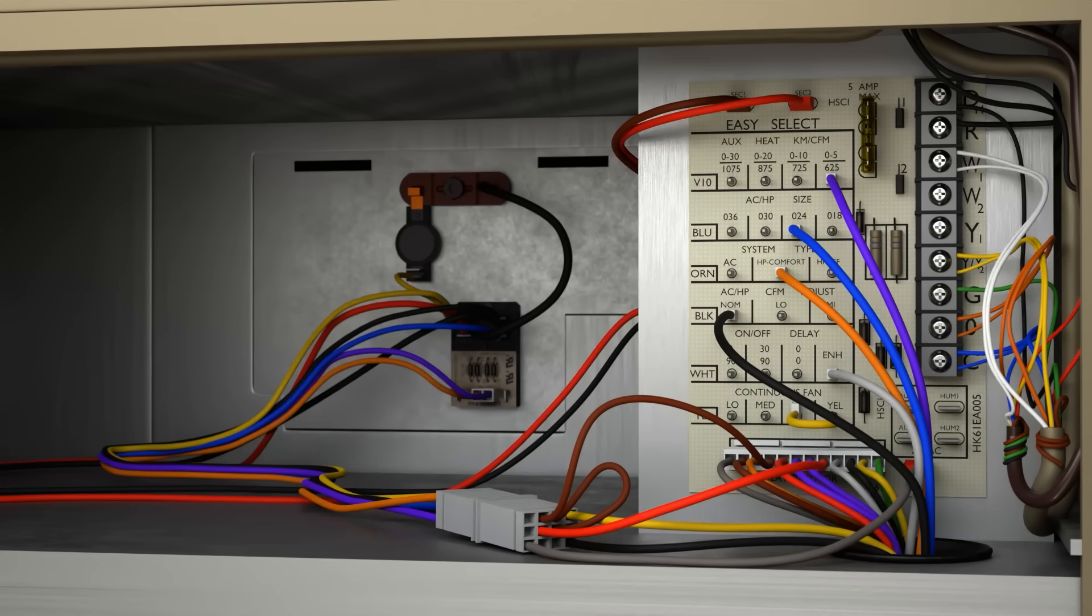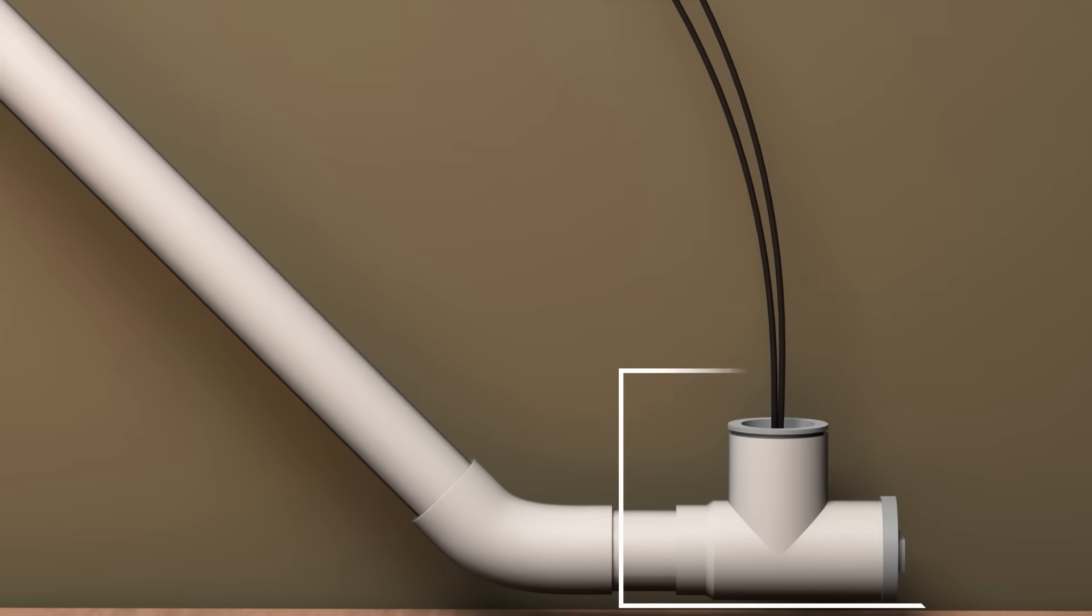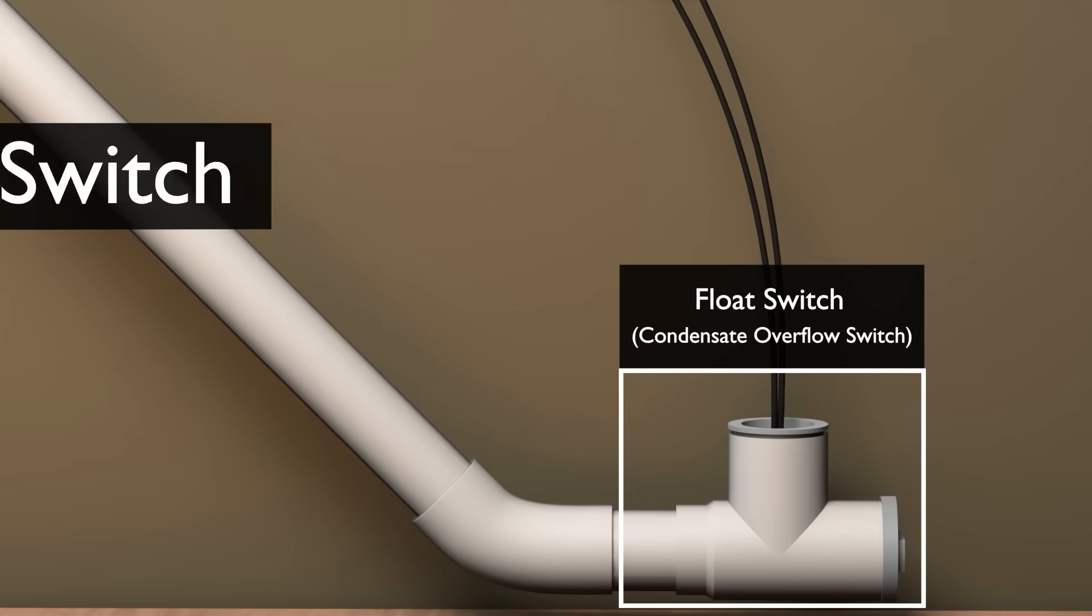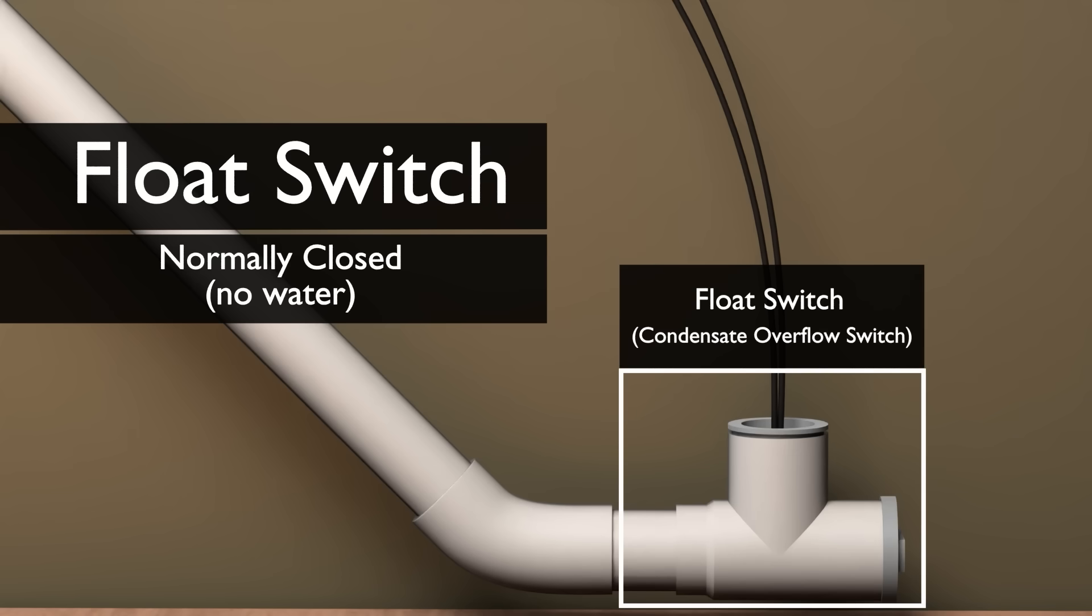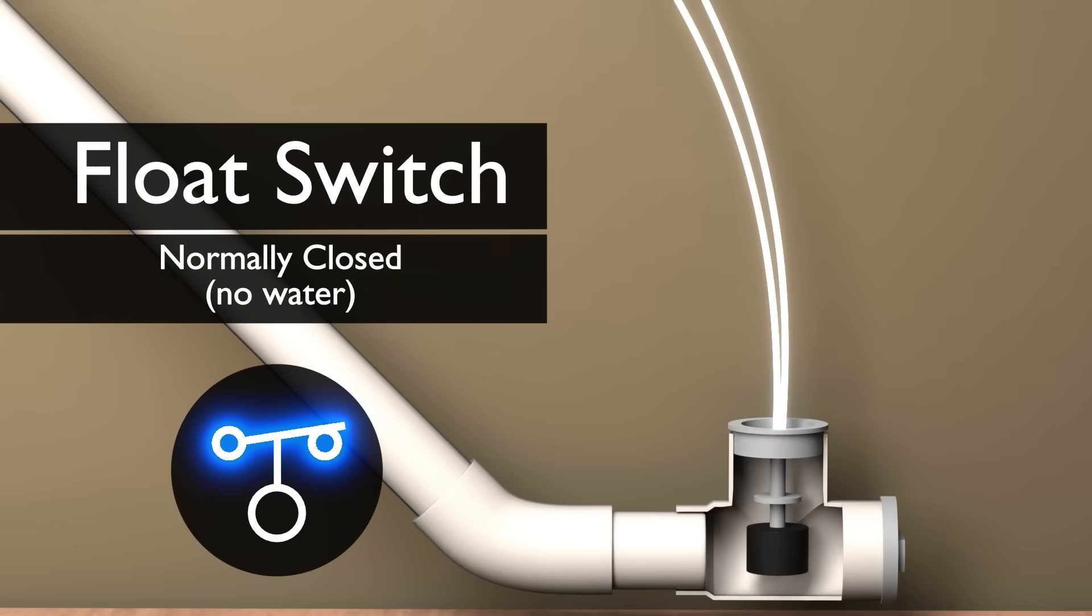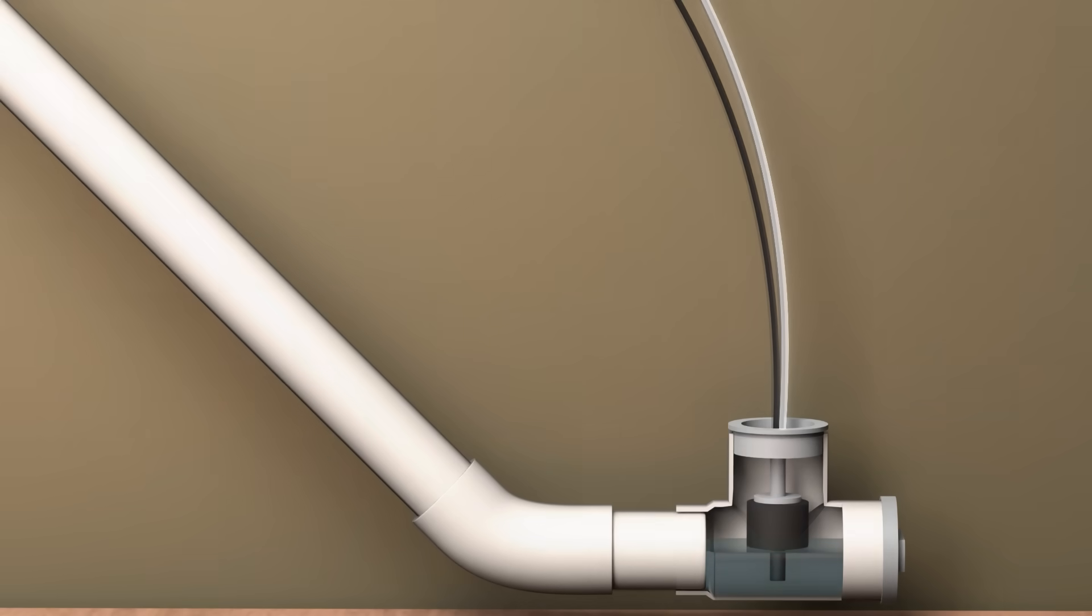A common component in a residential air conditioning system is the float switch or the condensate overflow switch. These switches are normally closed. When they fill with water, the switch opens, which breaks the circuit and shuts off the system.